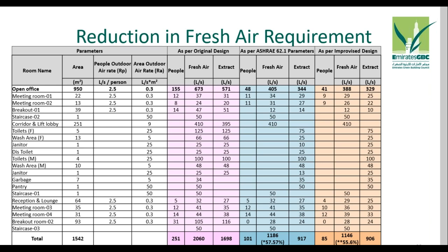So whenever we are presenting the whole scenario, we are first of all establishing what was the case for one floor and how it was applied to the whole building. The pink column notifies the original design. The blue column notifies the design parameters as per ASHRAE, and how, taking the ASHRAE parameters, it can be further improvised has been mentioned in the orange columns.